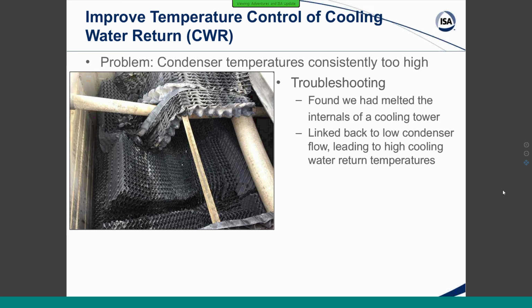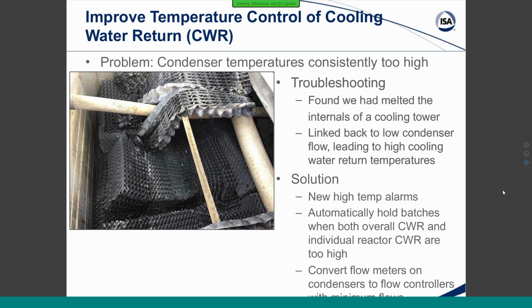But we linked all of this back, did some root cause analysis, and found that some of the operators were turning down the flow to the condensers. We still have not figured out why, but they were turning that down. And this was leading to high cooling water return temperatures, which was damaging the packing, which was causing high cooling water supply temperatures, which was causing even higher cooling water return temperatures, and it just turned into this vicious loop that basically destroyed the whole inside of the tower. So we put the tower back together and got it all fixed up.